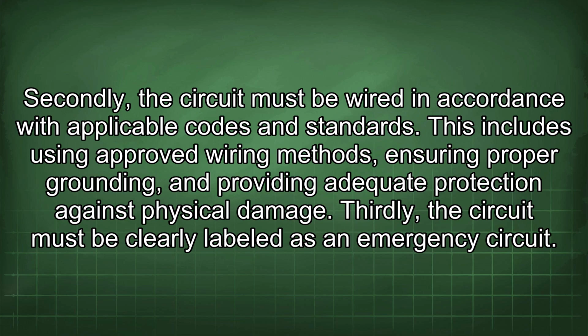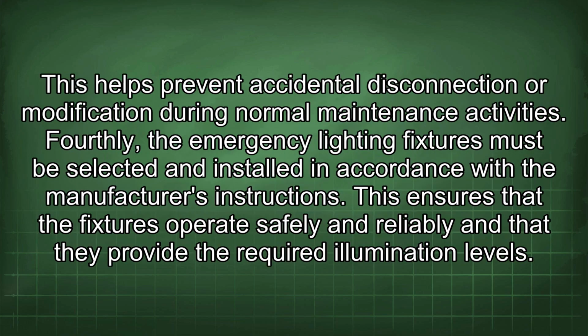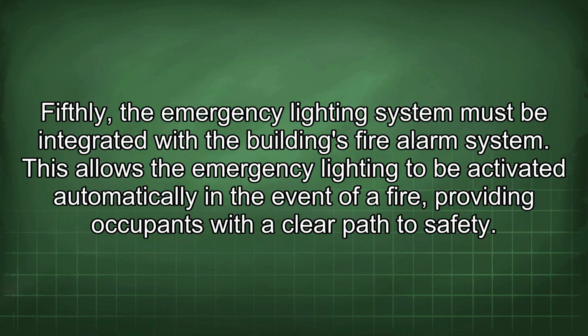Thirdly, the circuit must be clearly labeled as an emergency circuit. This helps prevent accidental disconnection or modification during normal maintenance activities. Fourthly, the emergency lighting fixtures must be selected and installed in accordance with the manufacturer's instructions. This ensures that the fixtures operate safely and reliably and that they provide the required illumination levels. Fifthly, the emergency lighting system must be integrated with the building's fire alarm system. This allows the emergency lighting to be activated automatically in the event of a fire, providing occupants with a clear path to safety.